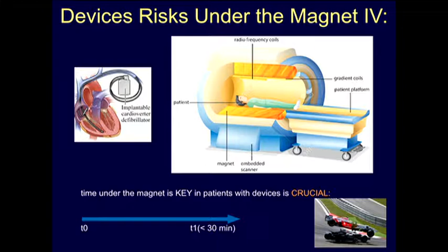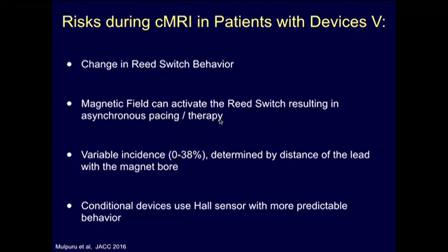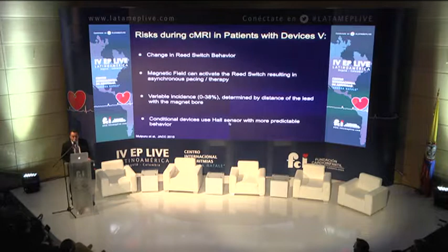There can also be changes in the reed switch. The magnetic field can activate the reed switch, which results in asynchronous pacing, or in therapy in patients with defibrillators. Variable incidence, usually higher, determined by distance of the lead and the magnet bore. Conditional devices use Hall sensor so that the reed switch becomes more predictable.